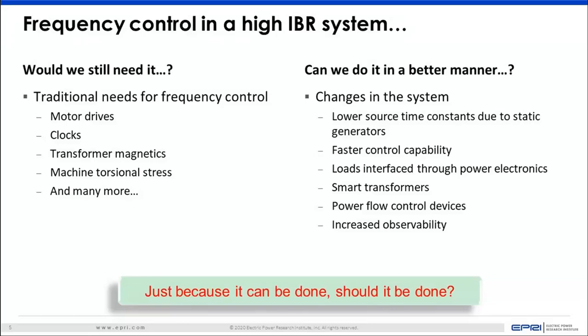But because you are removing the mechanical time constants, it allows us to do this in a much better manner, where you have a lower source time constant and faster control capability. You could have smart transformers in the network. You could have increased observability. But after all that, we come down to the final question: just because it can be done, should it be done? And there's no general answer for that. It depends on a variety of other factors. And what we can show here is just how it can be done. And the following question, of whether it should be done, will have to come up later.